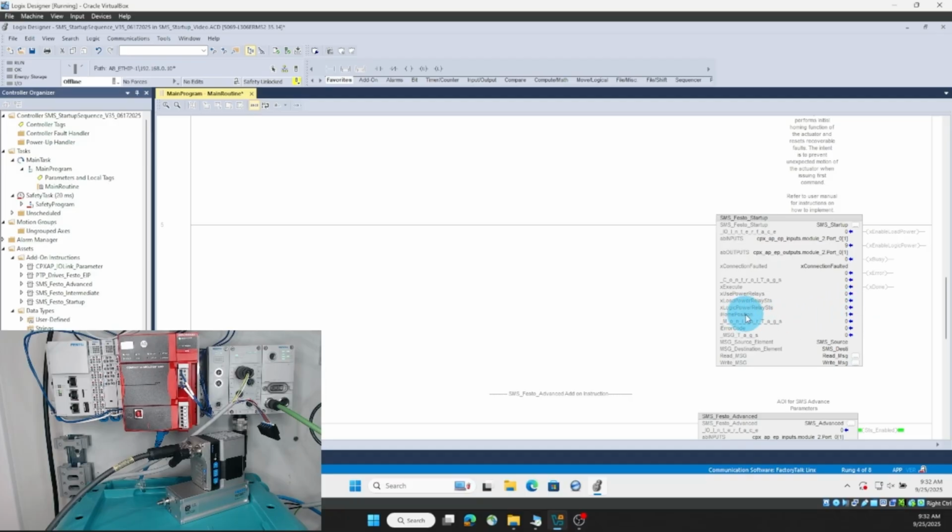Now for this I home position, I have 3 options. I can set this to 1, 2, or 3, meaning 1 is that it ends the sequence in the in position, 2 ends in the intermediate position, and 3 ends in the end position. Either one of these work, it just defines your initial conditions.